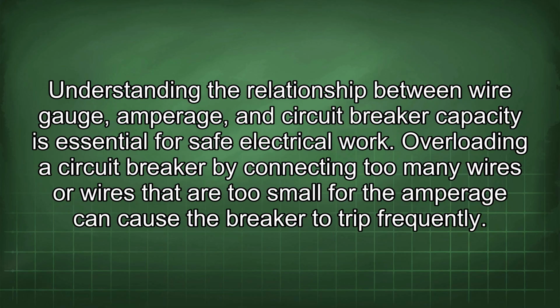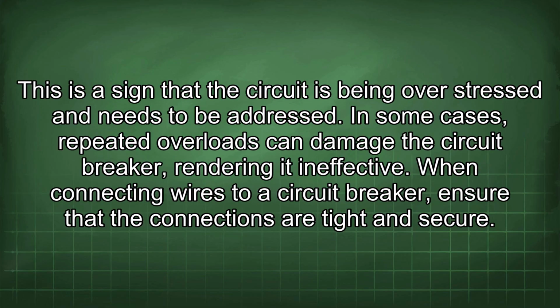Understanding the relationship between wire gauge, amperage, and circuit breaker capacity is essential for safe electrical work. Overloading a circuit breaker by connecting too many wires or wires that are too small for the amperage can cause the breaker to trip frequently. This is a sign that the circuit is being overstressed and needs to be addressed. In some cases, repeated overloads can damage the circuit breaker, rendering it ineffective.